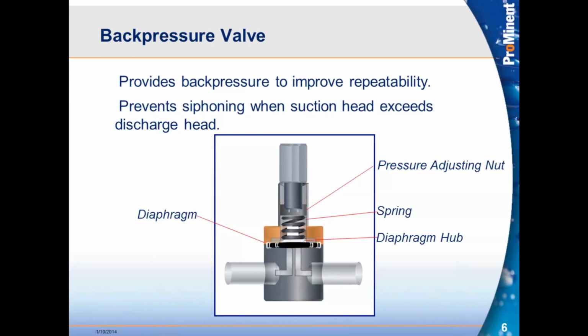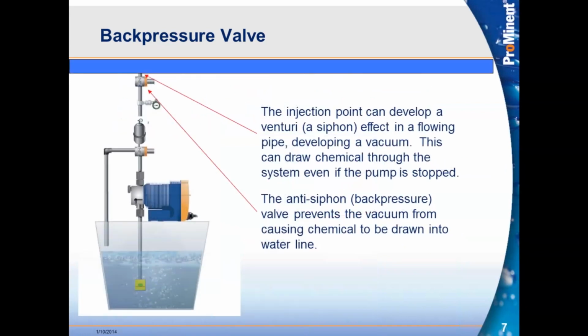It's threaded, so we thread it down in further, and it's compressing that spring. So now we're going to have to push up on that diaphragm harder with more force, that's our pressure, to open it up so that we can flow through. So that's nothing more than that. Now, a back pressure valve, this is a 2-port device. Now, we do commonly use a 2-port back pressure valve as a pressure relief as well. We just have that installed before the back pressure valve, and we adjust it higher than what we have the back pressure valve set to. So now it's the pressure relief in that case. We'll see some graphics showing that as well.